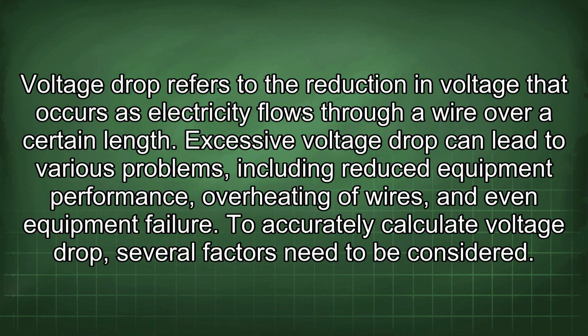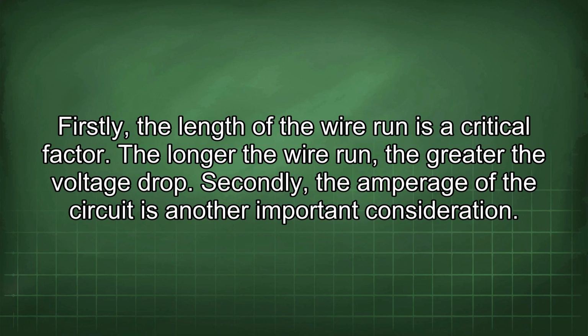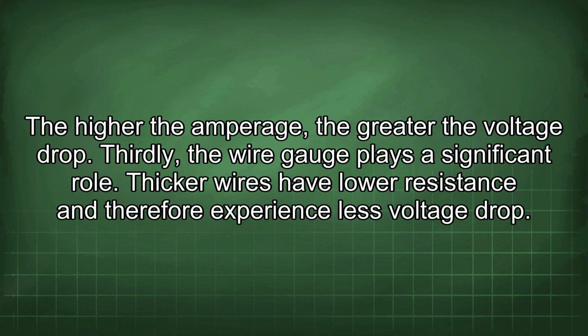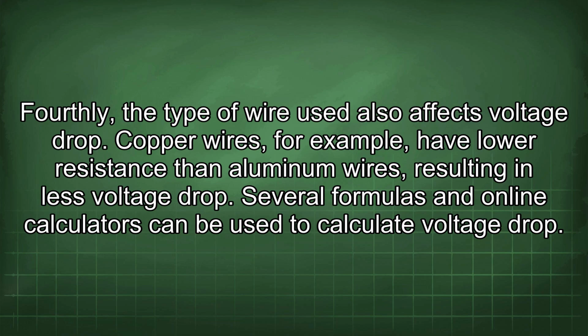To accurately calculate voltage drop, several factors need to be considered. Firstly, the length of the wire run is a critical factor. The longer the wire run, the greater the voltage drop. Secondly, the amperage of the circuit is another important consideration. The higher the amperage, the greater the voltage drop. Thirdly, the wire gauge plays a significant role. Thicker wires have lower resistance and therefore experience less voltage drop. Fourthly, the type of wire used also affects voltage drop. Copper wires, for example, have lower resistance than aluminum wires, resulting in less voltage drop.